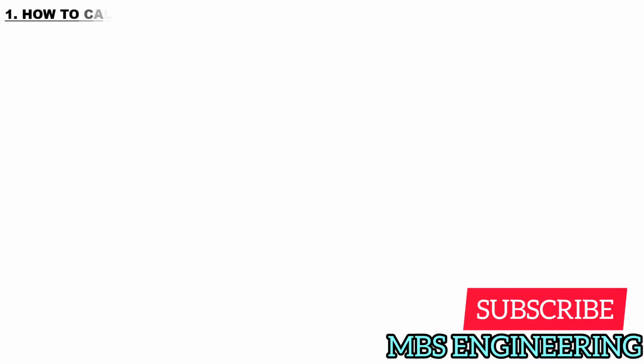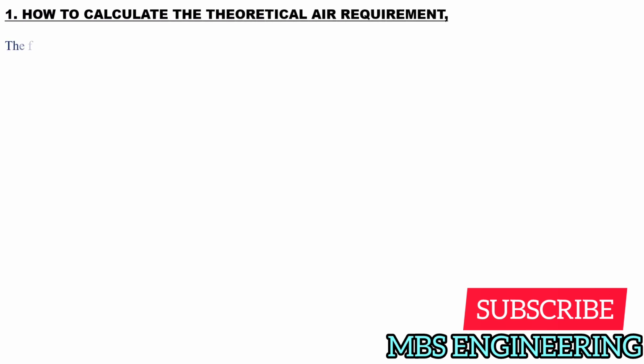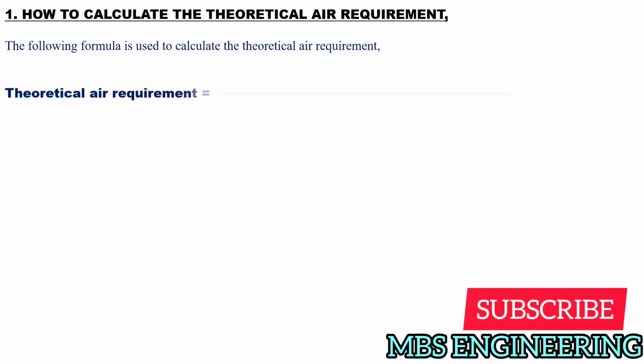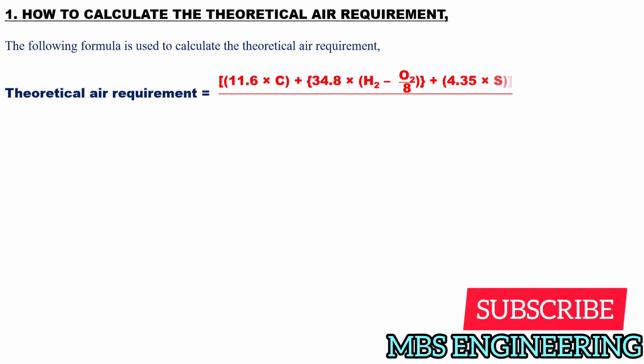Next, we will learn and understand the formula used to calculate the theoretical air requirement. The following formula is used to calculate the theoretical air requirement. Theoretical air requirement is equal to 11.6 times C plus 34.8 times (H2 minus O2 divided by 8) plus 4.35 times S, and then the obtained value is divided by 100. Its unit is measured in kilograms per kilogram of fuel.